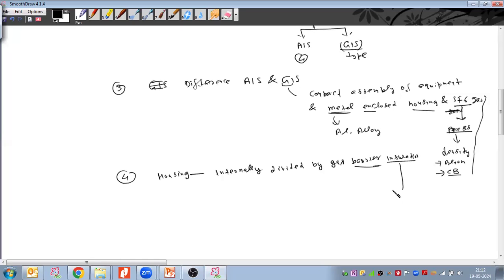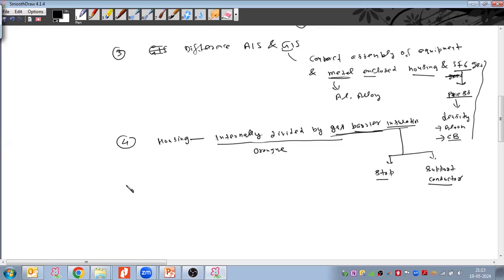We discussed that there are two kinds of insulator we use. One is the gas barrier insulator that stops the gas, that does not allow the gas to pass, and the other is the support insulator that allows the gas to pass, but it just supports the conductors, right? So the housing is internally divided by using the gas barrier insulators. This gas barrier insulator is also visibly indicated by the manufacturer in a different color. Generally we take the orange color, right?